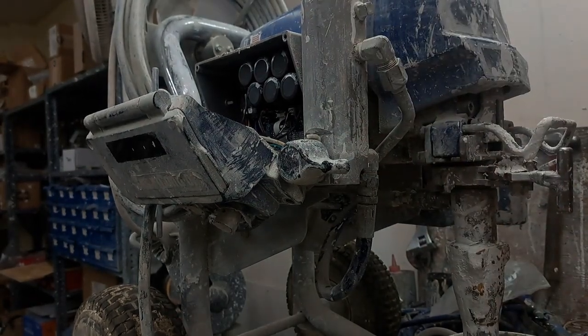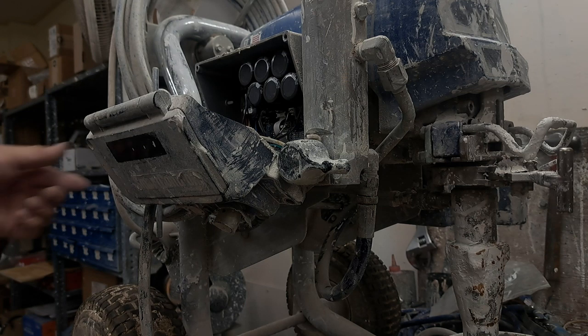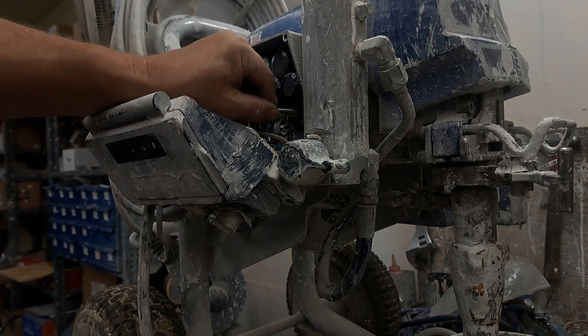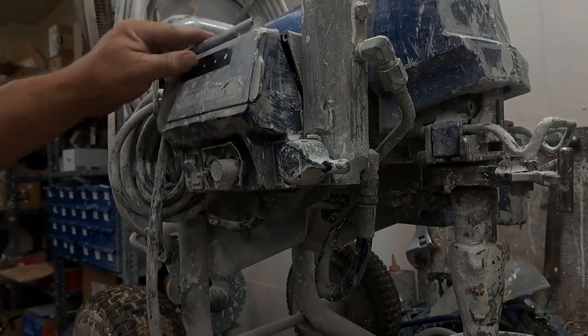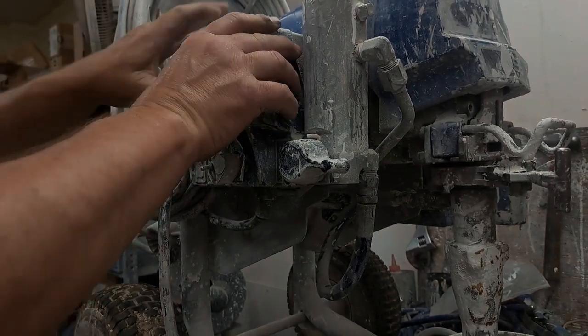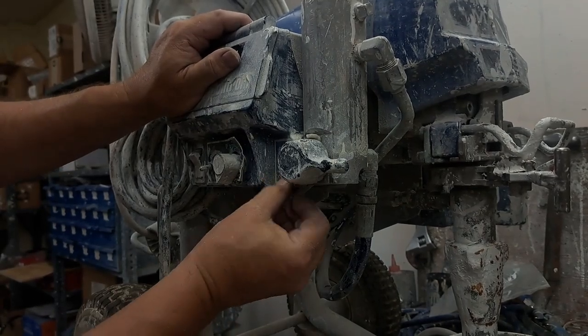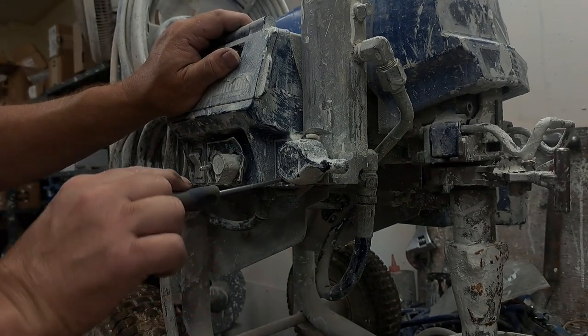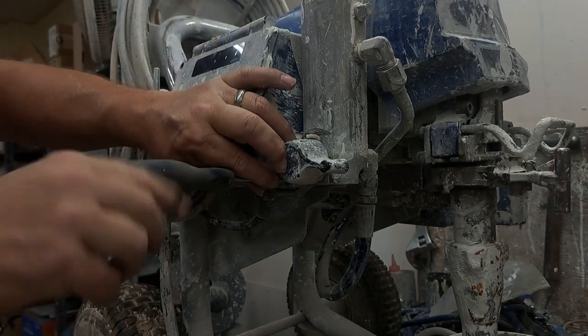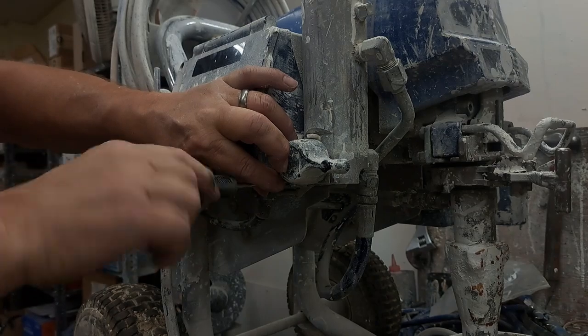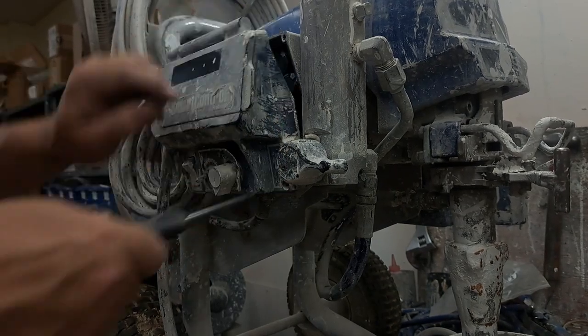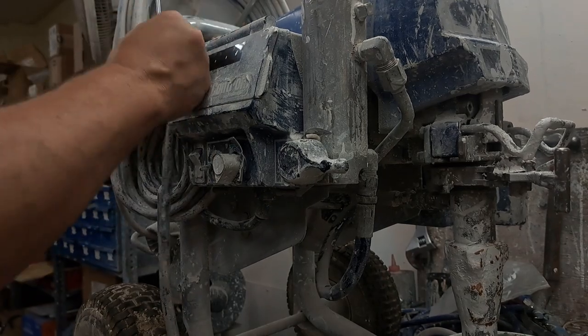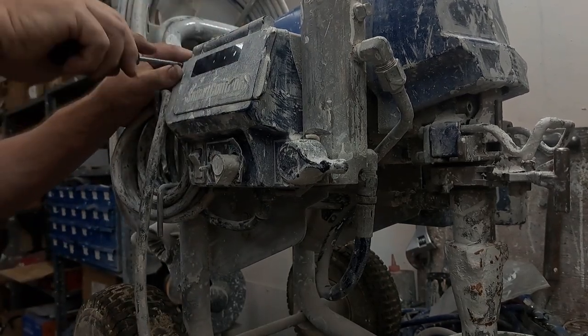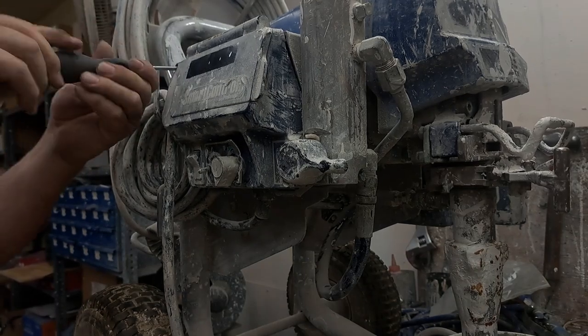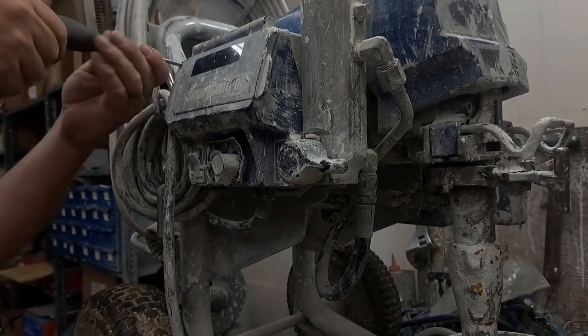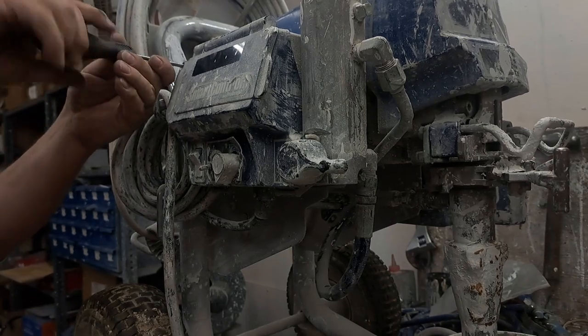Tighten it up. Now we're going to go back over here to the board. We're going to plug this back in. It only goes in one way. Click. Push this up. Screw it back in place. Once we got all this back together, we turn it on and the pressure is down low. It should say 0 or something like that. It's not going to show 4,400 psi like it did to begin with. If it does, we got another problem.